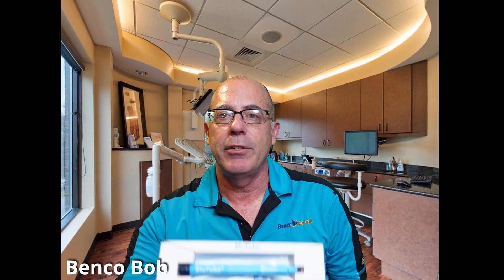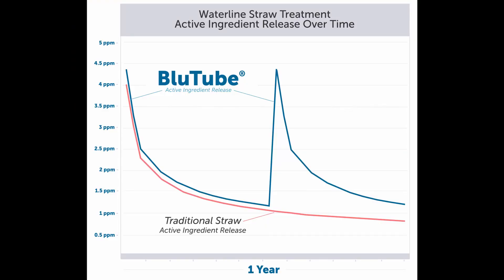As far as maintenance is concerned, you have a couple of options: you can use tablets or you can use straws. I prefer the straws since they are on all the time and you don't have to have anybody remember to put a tablet in the bottle every day. ProEdge makes the BluTube — it comes in a box of two, they're good for six months. Once you connect them up to your waterline, you can just forget about it for six months. At the six-month point you'll get a reminder, you shock the system and put the second straw on, and you're good for another six months. Yes, other manufacturers claim 12 months, but studies have shown that the efficacy of the active ingredient diminishes at about the six-month period.